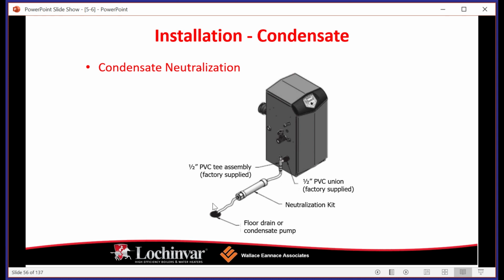You're going to run it through a neutralization kit. When it comes out of the neutralization kit, it is inert, right? It is now just regular water. The pH is correct. It's no longer dangerous to your building. It's no longer dangerous to the environment. The way a condensate neutralization kit works is essentially it's filled full of rocks, like pebbles, and this is limestone. So as the acidity of the water flows over these limestone rocks, the natural properties of the limestone counteract the acidity and it comes out the other side. Again, inert, safe to pump out into the public water supplies with no issues at all.